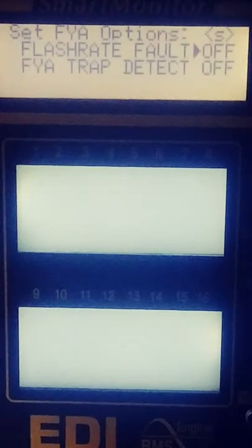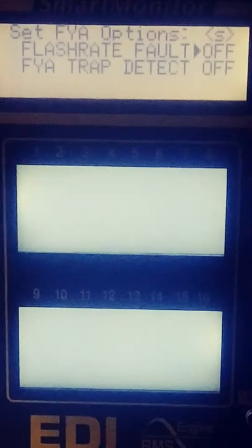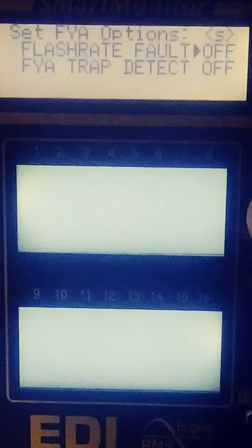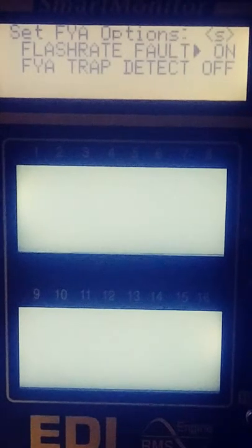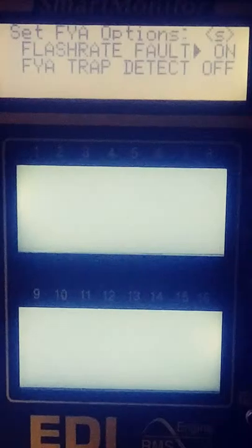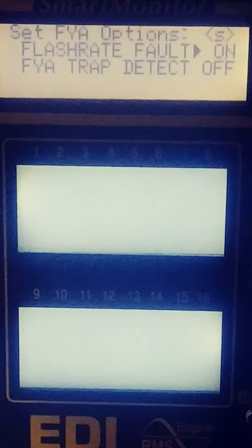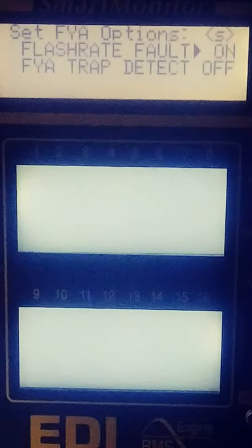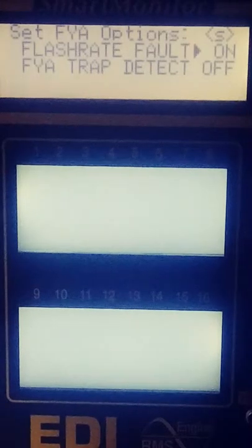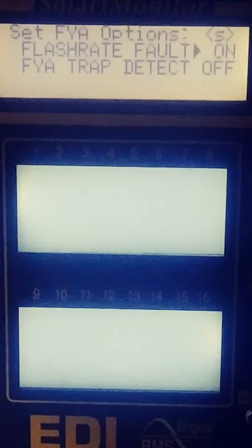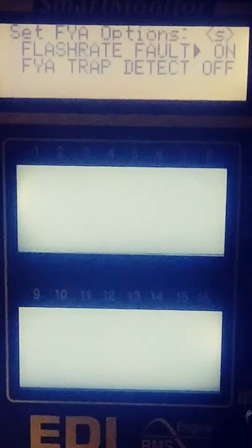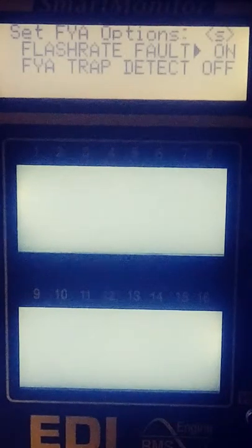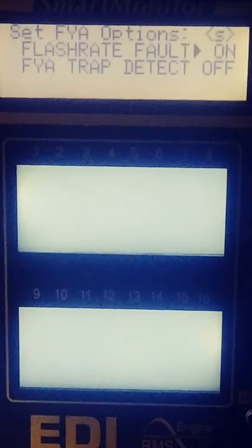Now it's going to ask you if you want your flash rate fault on. Go ahead and hit select for on. Your flash rate fault option enables the flashing yellow arrow output to be monitored for the lack of a flashing operation as well as monitoring to see if the output remains active longer than the fault time of 175 milliseconds.